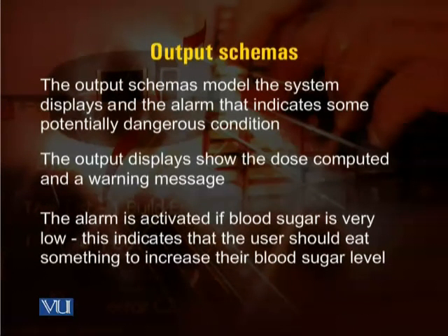Now here we have two things. I've talked about this alarm which says that the blood sugar level is very low, and it is an indication to the patient that the patient should take some sugar. We were using the same alarm to indicate that there is less amount of insulin left in the reservoir, so that the reservoir needs to be refilled. So we have the same alarm signal. Since it is an output from the device to the user, this is an output variable. It may be used in two different situations.